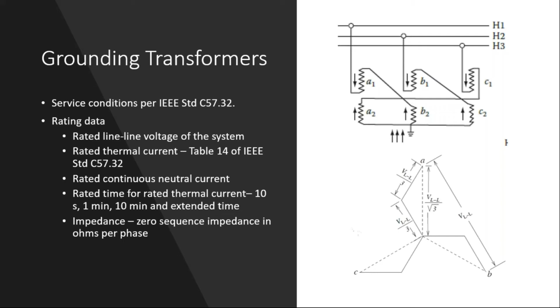Now A1 is wound in such a way that the ampere turns in leg 1 cancel each other, because the currents in A1 and A2 are flowing opposite to each other. This phenomenon happens only when there is a fault in the system. What it means is that the zigzag transformer operates when there is a fault. What is very important here is that the customer has to specify the continuous neutral current, the fault or thermal current, and how much time it flows in the transformer. So the transformer manufacturer does the calculations to meet the temperature rise requirement as per the standard during the fault current.